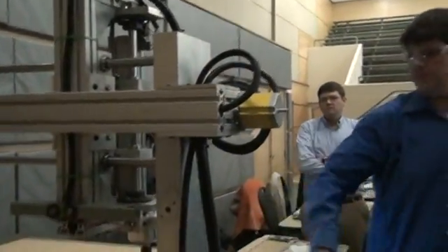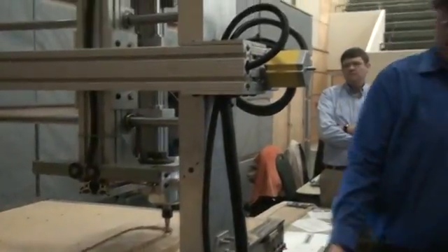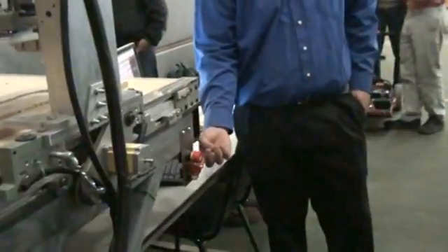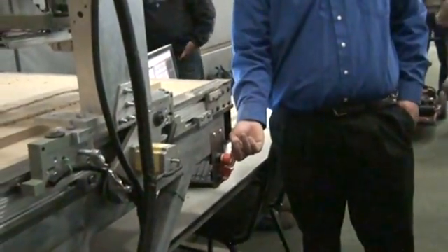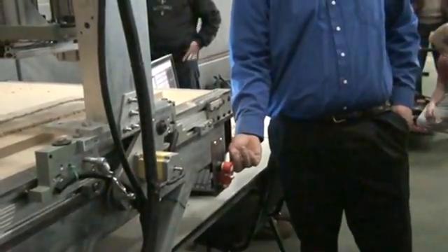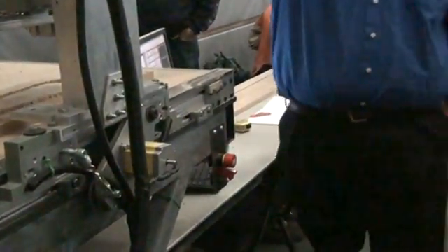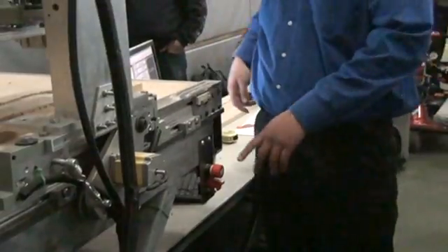Like I said, the problem is once that limit switch is hit, we have a one-way switch in here with a nice cover on it so it can never get hit. And when you're holding that switch up, you're overriding your whole limit system. So what that does for you is it allows you to get off your limit, because once that limit is hit, you can't ever leave it until you override that system.